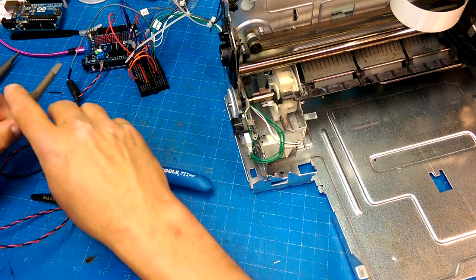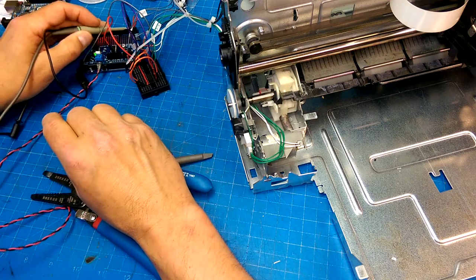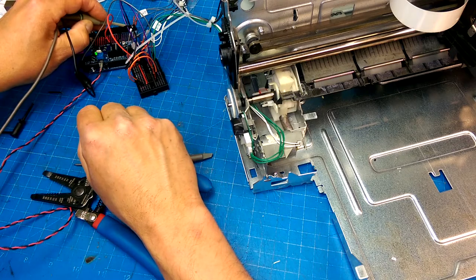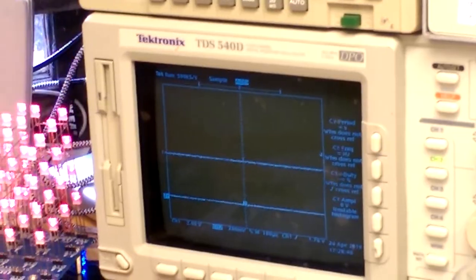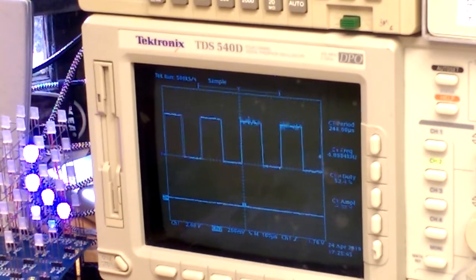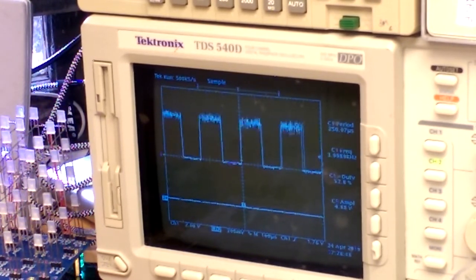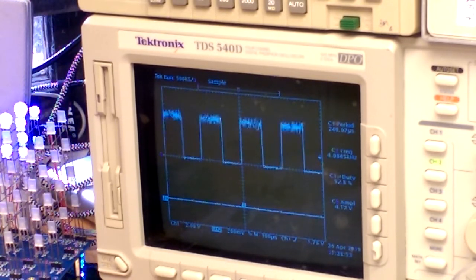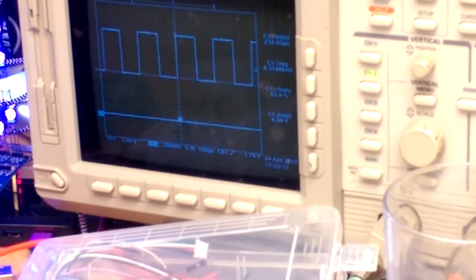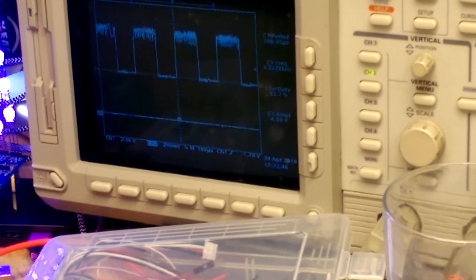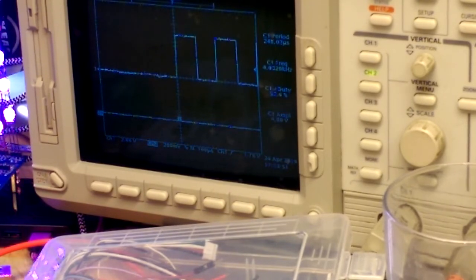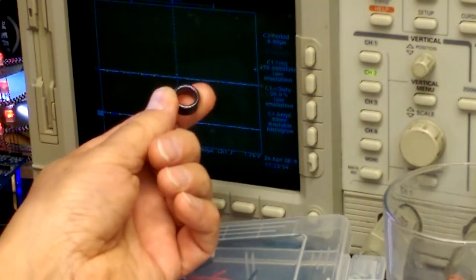It's noisy when the motor is running, but I don't have any ferrites on the motor either. Yeah, it's noisy when the motor runs. So I'm going to throw some ferrites on the motor cables, the motor leads, and see if that helps. That looks better. There it is without again. And there's all that noise on the line, but if you just throw a little toroid, loop the wire motor windings through, it cleans that noise up.